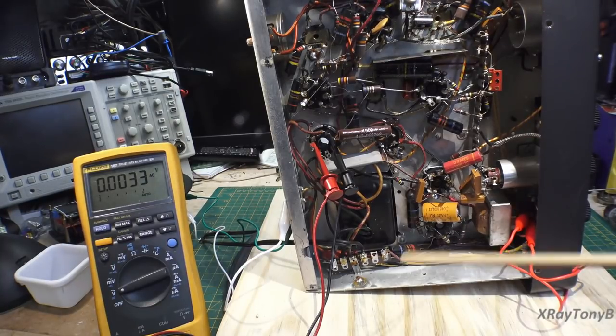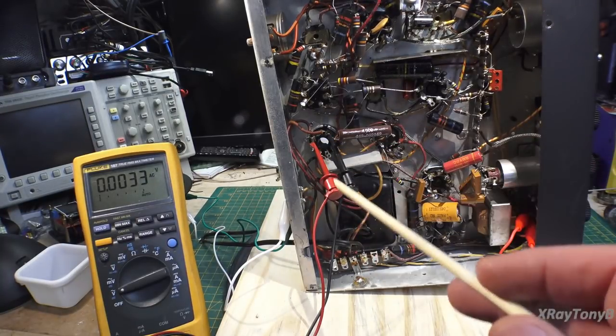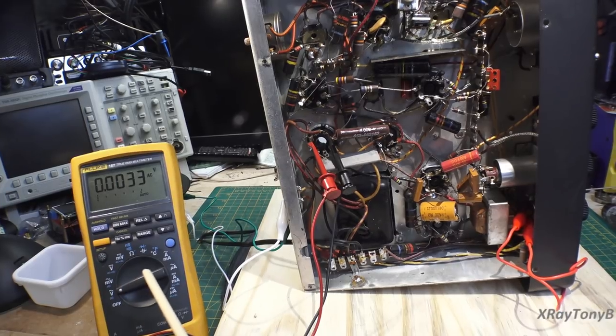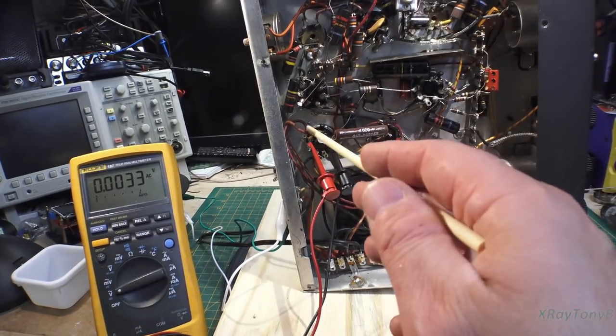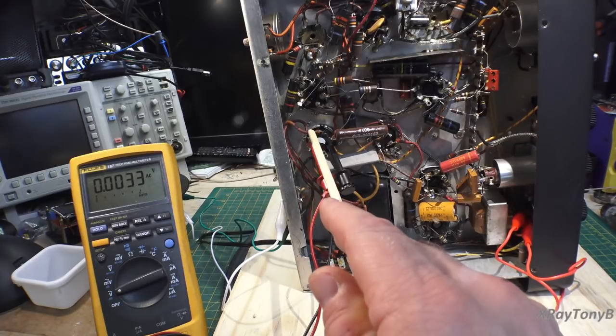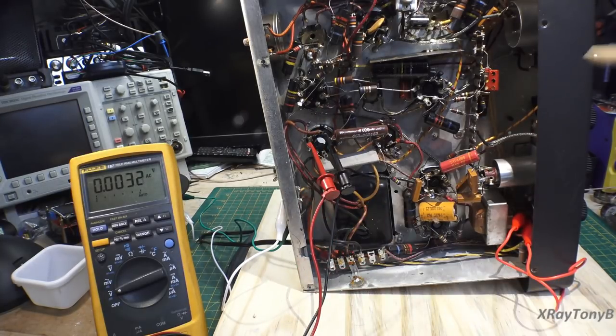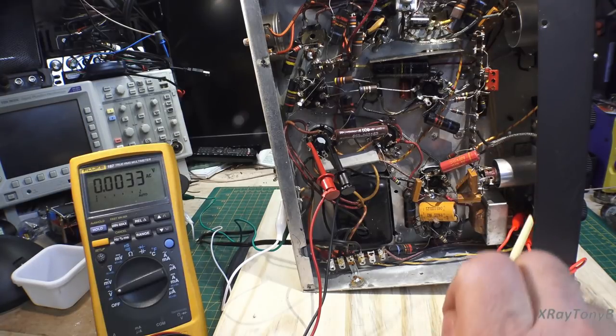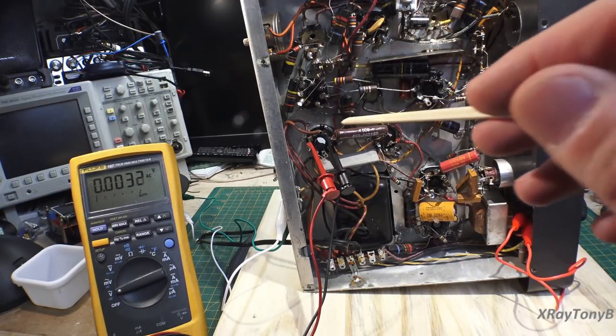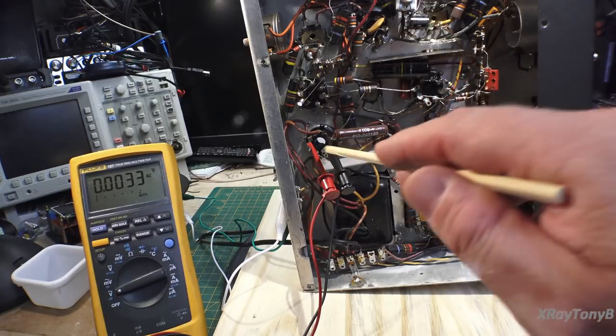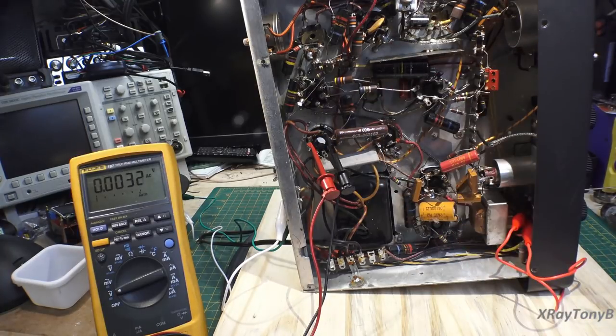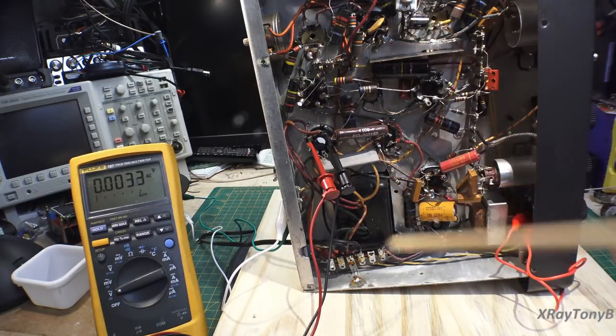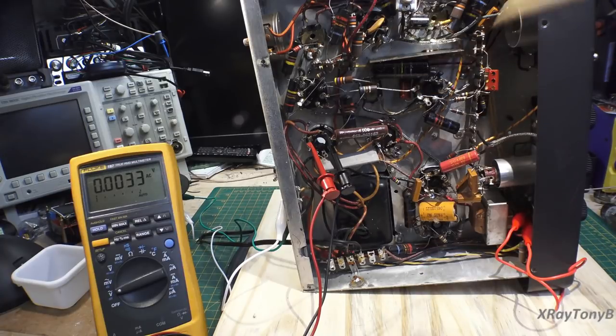Okay, now we have the tube pulled out, and we have our voltmeter set to AC volts, looking across the output of the high voltage windings first. As you can see, I jumpered out that switch. All we care about right now is to see if the winding is good. Then if these are good, we're going to move over to our filament windings and check them.